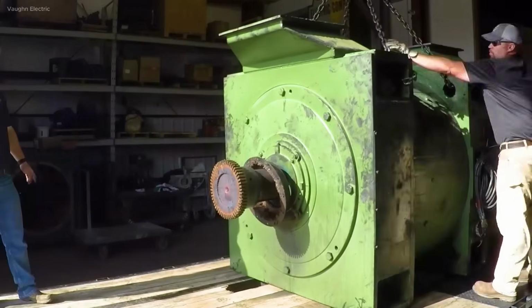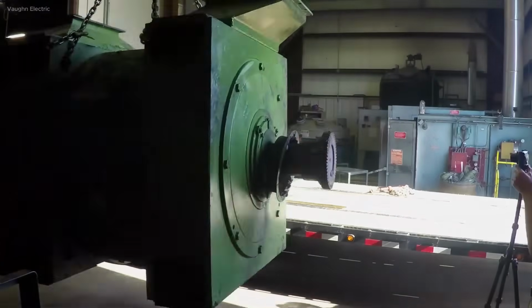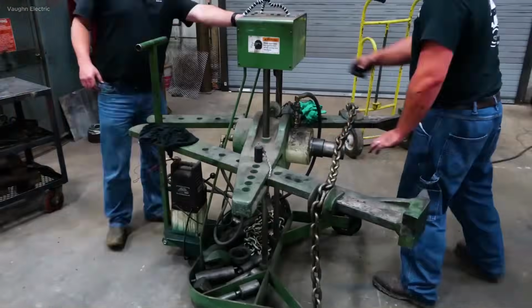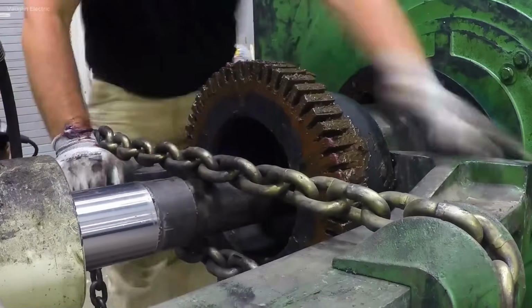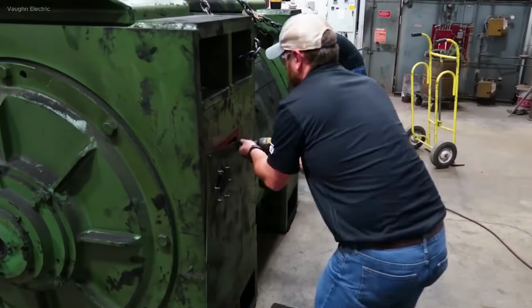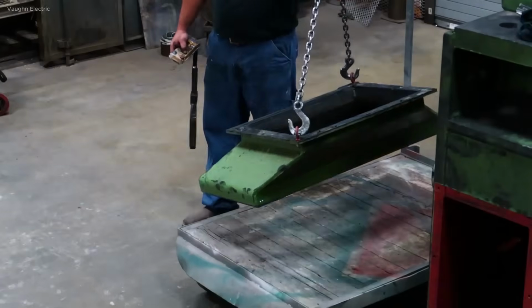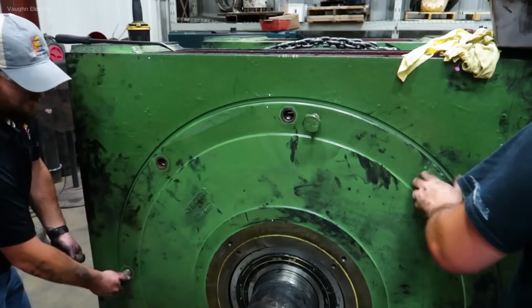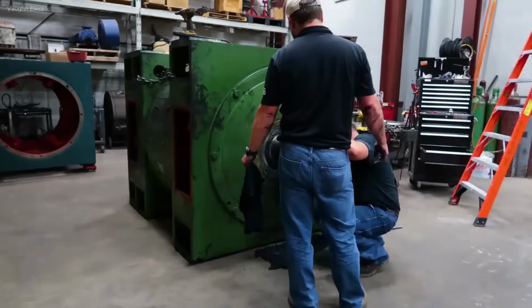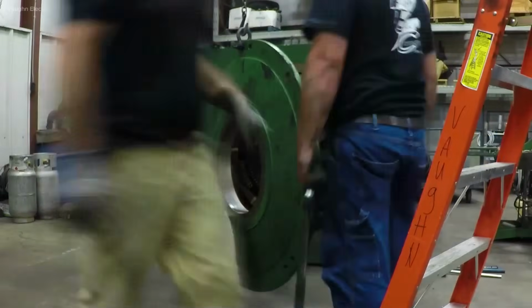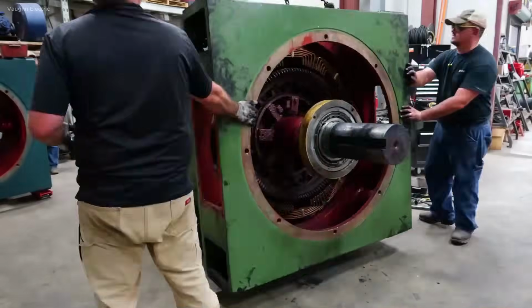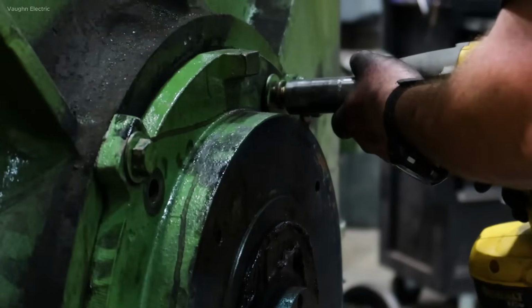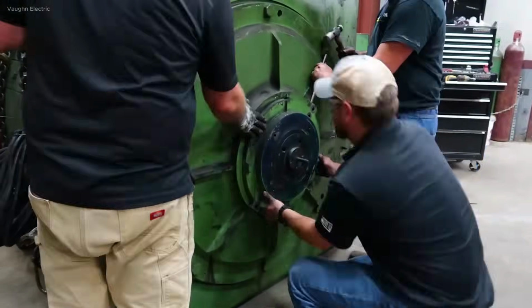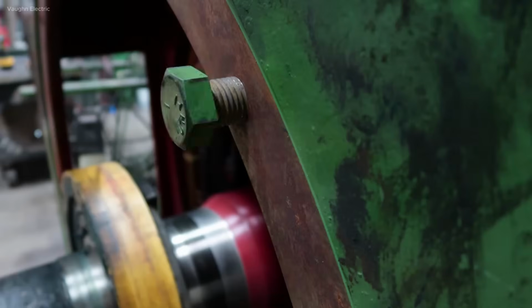The electric motor restoration process begins with a comprehensive disassembly. The motor is first carefully lifted using an overhead crane and positioned on a secure workbench. The end bells are removed using impact wrenches and pullers, followed by the detachment of the rotor from the stator. Technicians measure and record shaft runout and housing bore dimensions for alignment references. All fasteners and shims are labeled and stored systematically for reassembly.